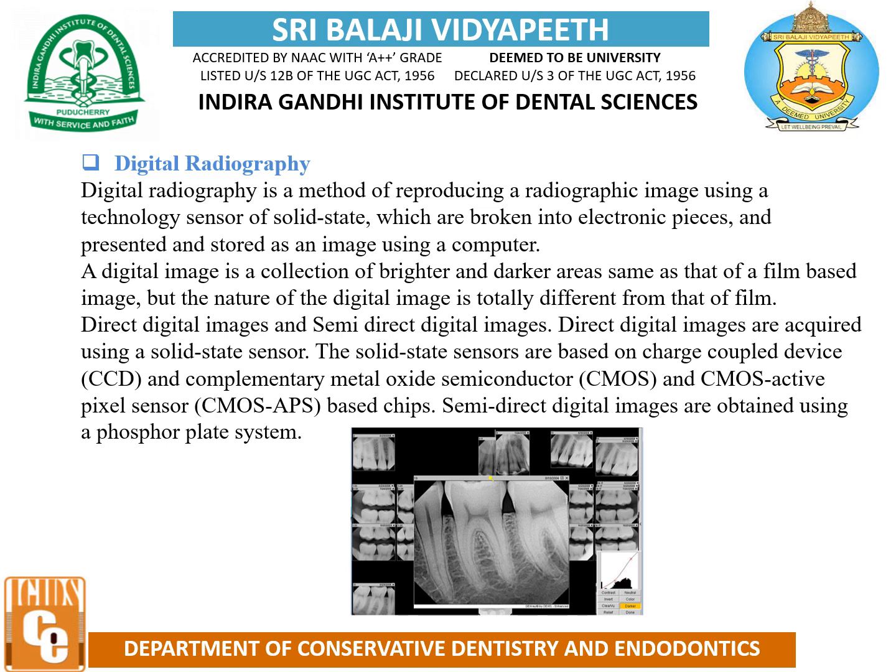Coming to digital radiography. Digital radiography is a method of reproducing a radiographic image using a solid-state sensor, where the image is broken into electronic pieces and presented and stored as an image using a computer. A digital image is a collection of brighter and darker areas same as that of a film-based image, but the nature of the digital image is totally different from that of the film.